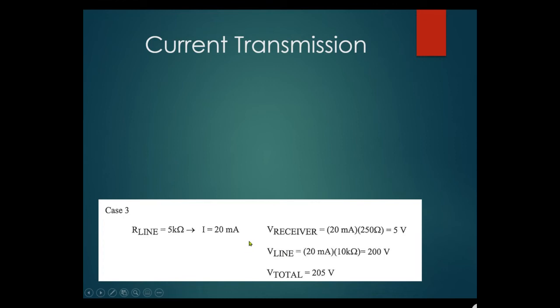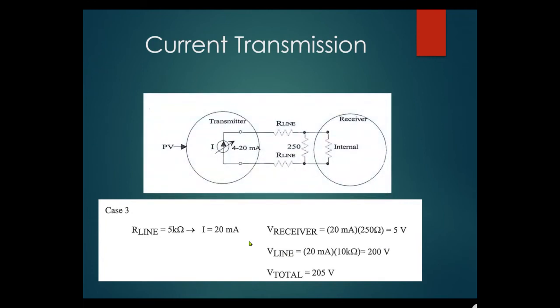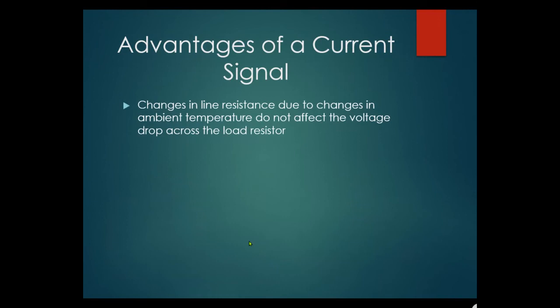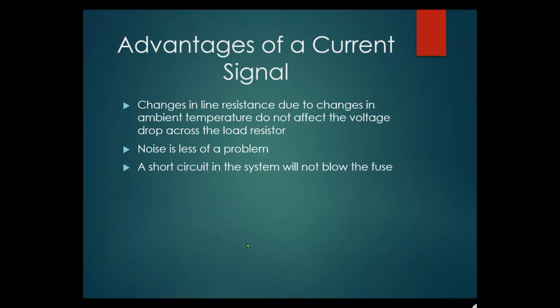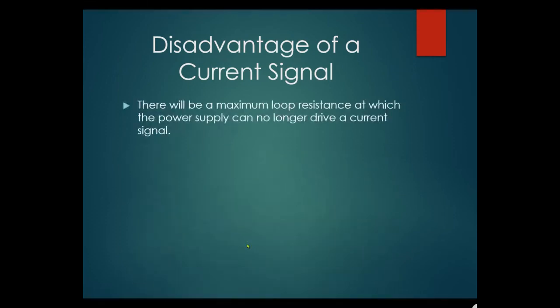Advantages of a current signal: changes in line resistance due to ambient temperature changes do not affect the voltage drop across the load resistor. Noise is less of a problem — the 1 to 5 volts is dropped across the 250 ohm resistor at the receiver. A short circuit won't blow a fuse because it's such a low current. Disadvantage: there is a maximum loop resistance at which the power supply can no longer drive the current signal — too much resistance means not enough voltage to push 4 to 20mA through.